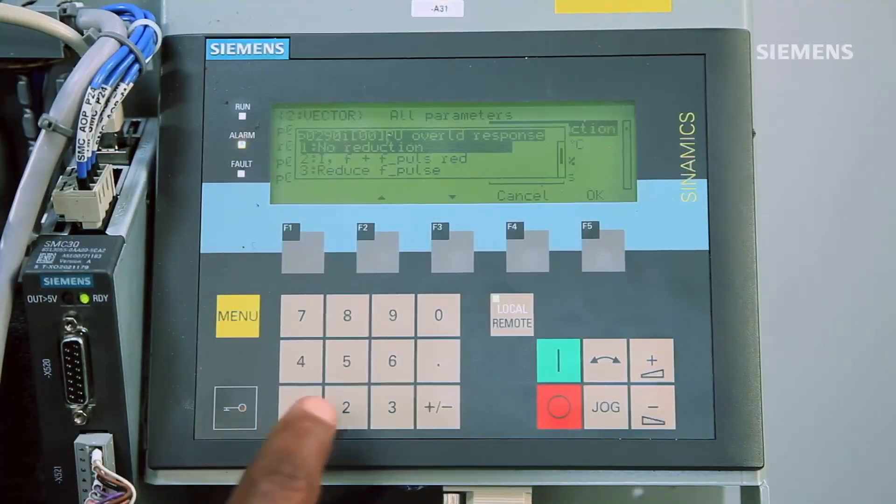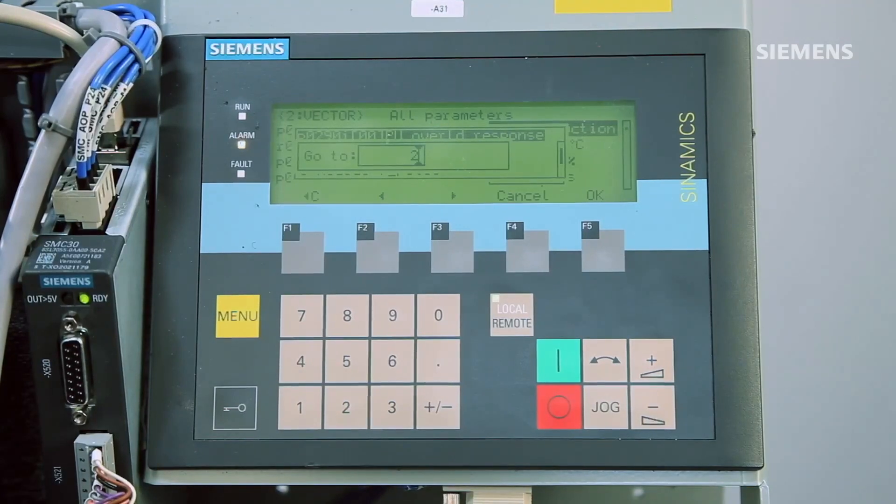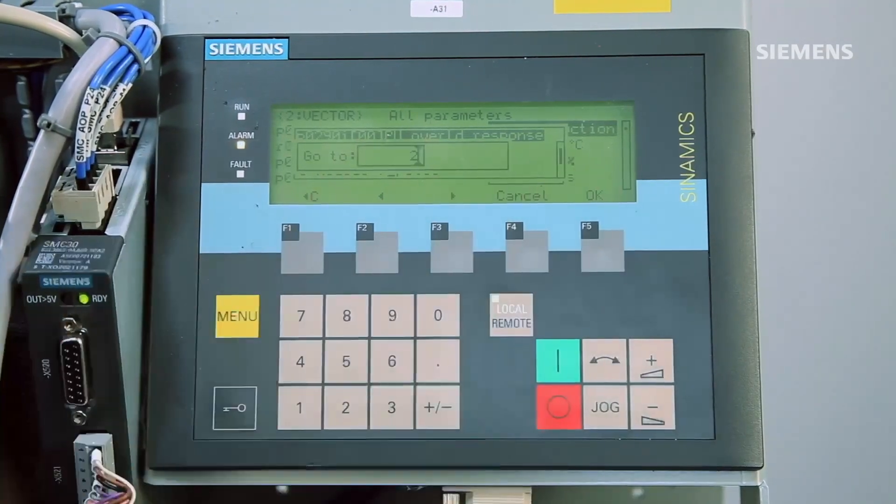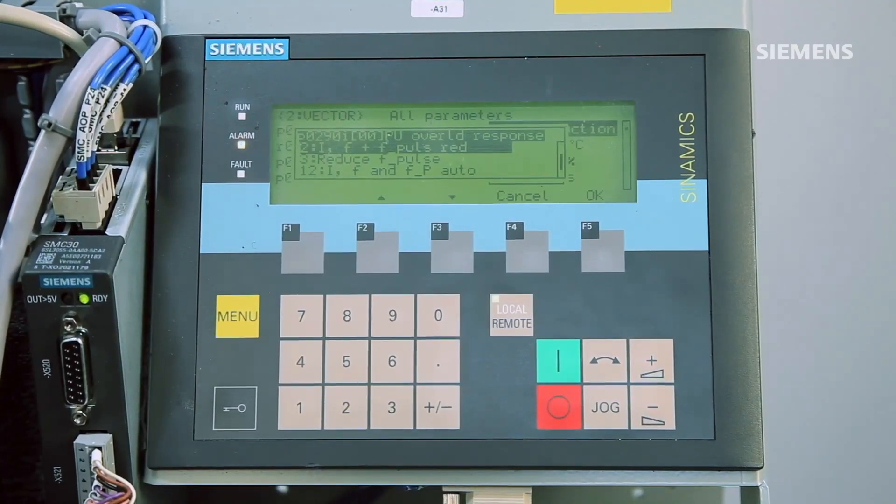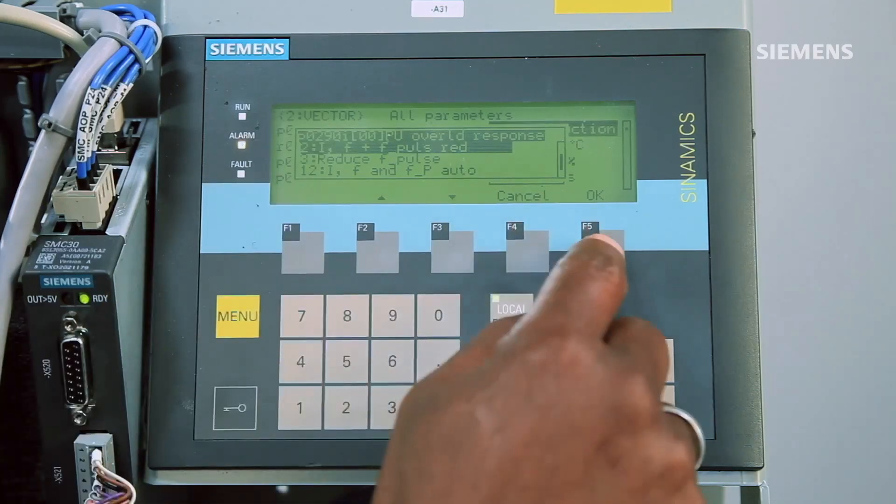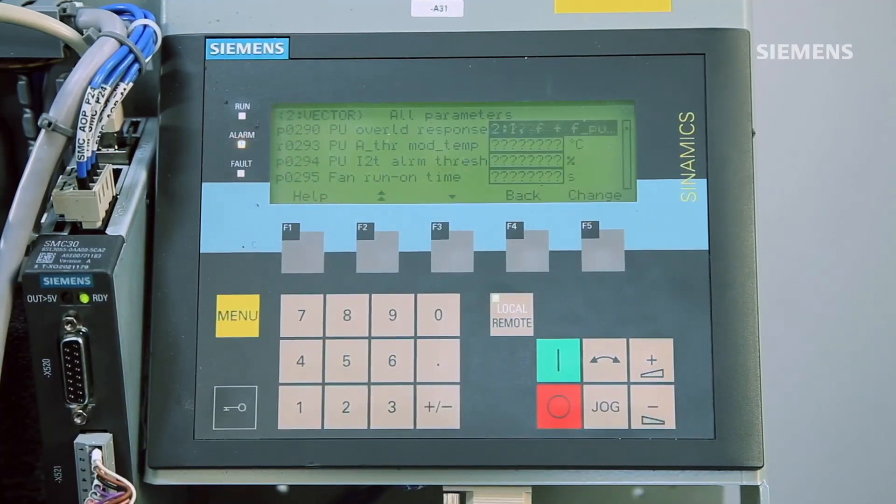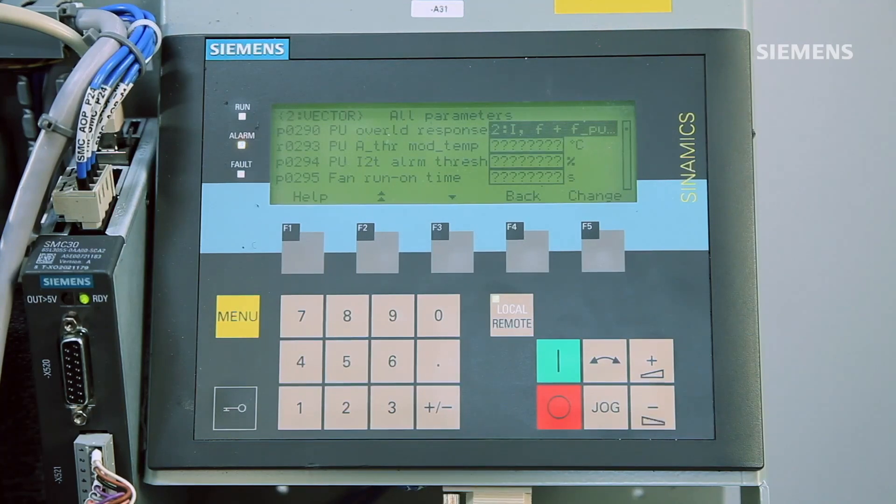If we set parameter 290 to 2, the drive will do a combination of lowering either output current or output frequency and lowering pulse frequency. So setting parameter 290 to 2 will be a combination of both 0 and 3.